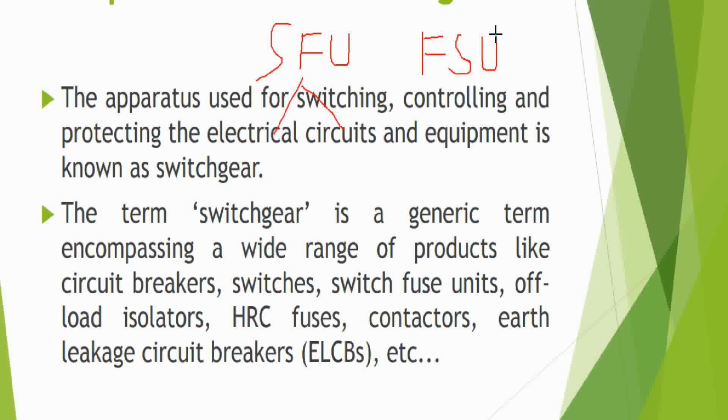When we operate the breaker, the contacts get closed through the switch and then the supply passes through the fuse unit to the output. In a fuse switch unit, there is no separate fuse and switch; the fuse itself acts as the switch. SFU is used to trip the circuit, particularly for high capacity tripping.